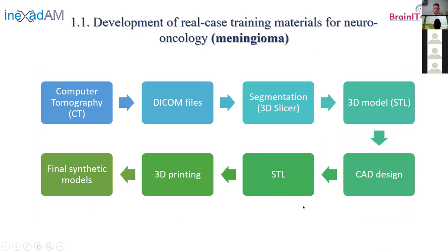For the segmentation of the skull, we started from CT images and performed segmentation in 3D Slicer. We also performed segmentation of the tumor. What we wanted was the mold of the tumor, so we added 10 mm thickness and removed the internal part to obtain a hollow that would serve as the mold for pouring the tumor-mimicking material. I will explain the design and manufacturing steps in more detail.